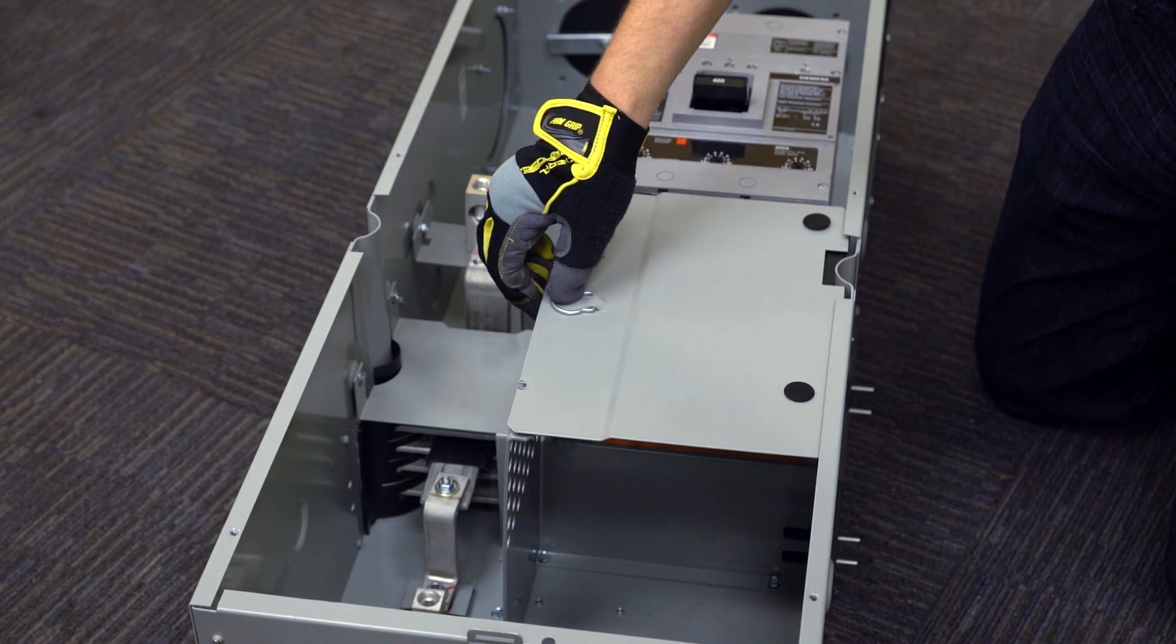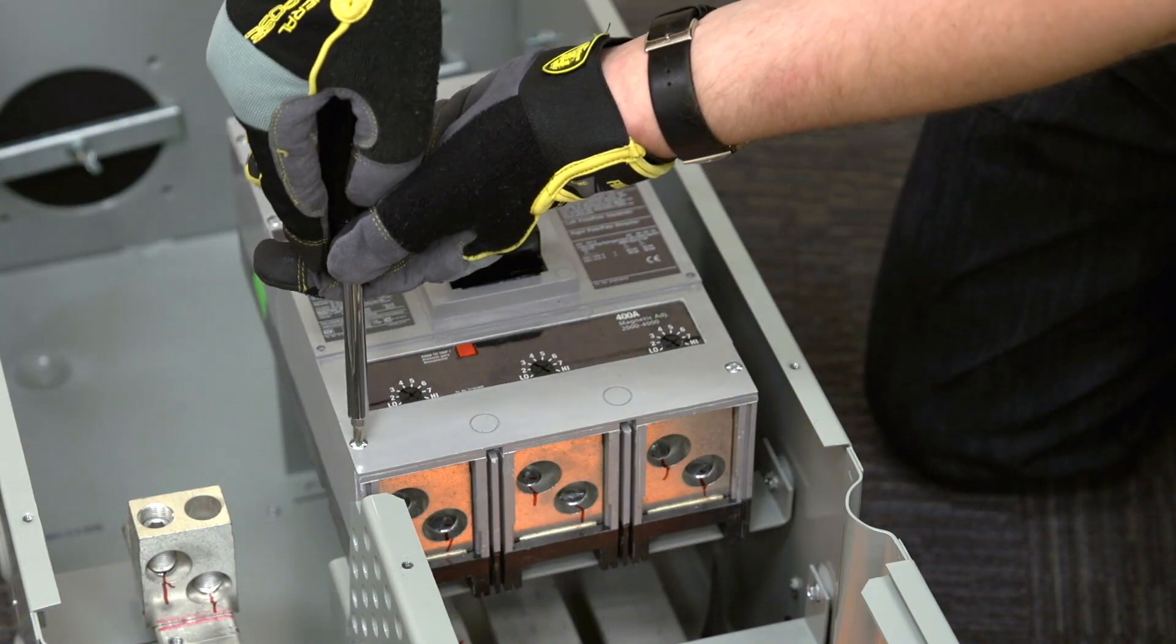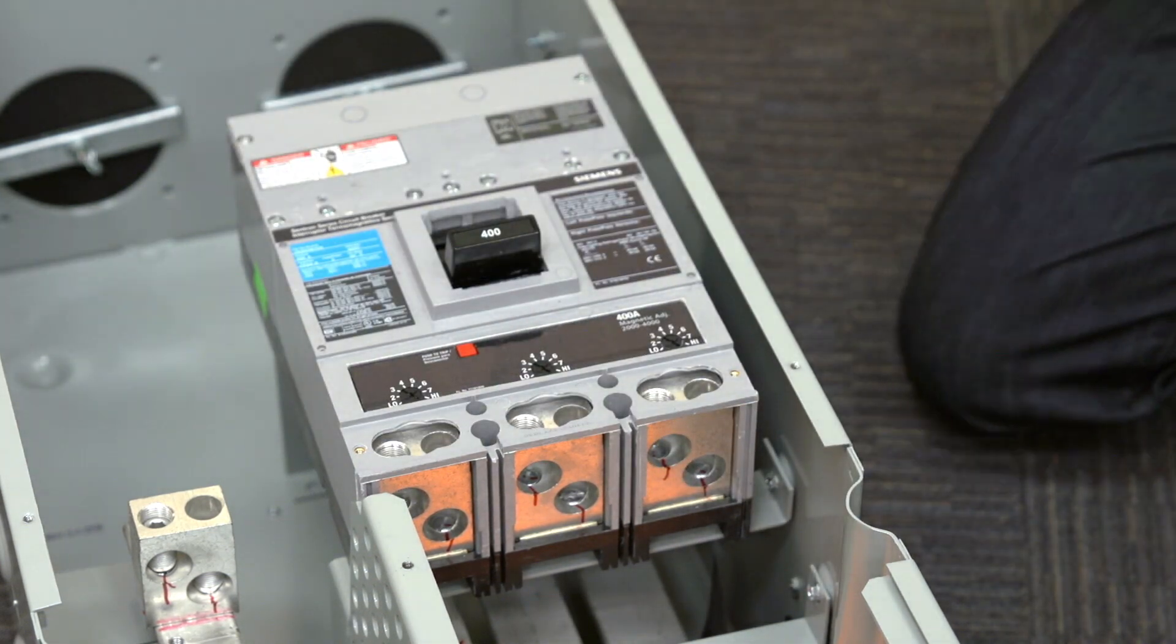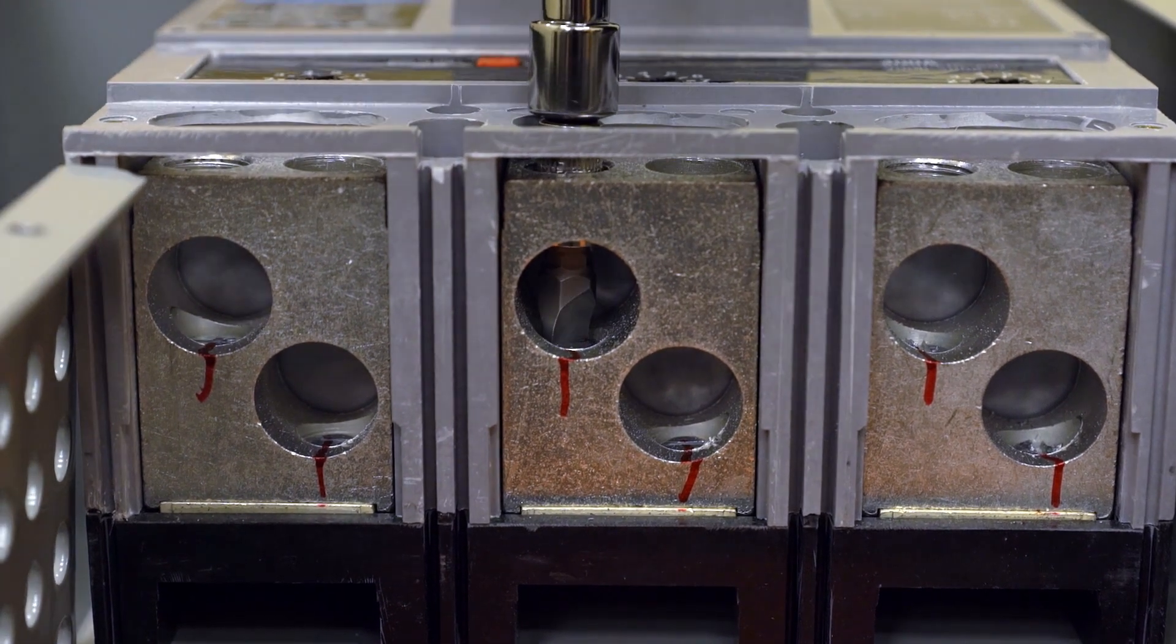Sometimes a job may call for a unique lug solution. If compression lugs, a NEMA stud kit, or larger lugs than what come factory installed are required, then a lug landing pad can help in these situations.